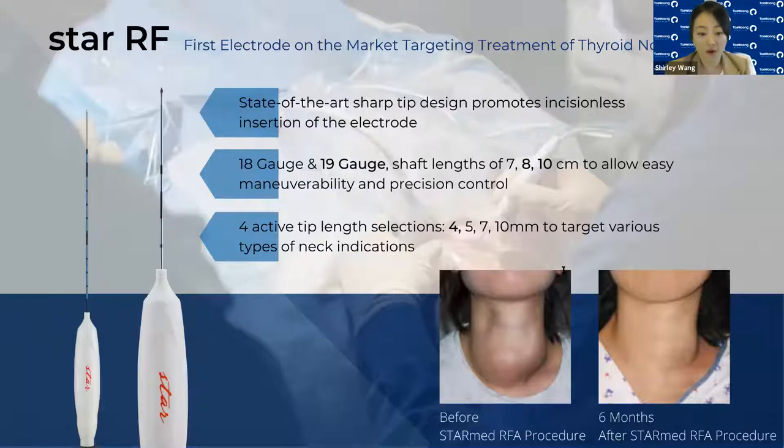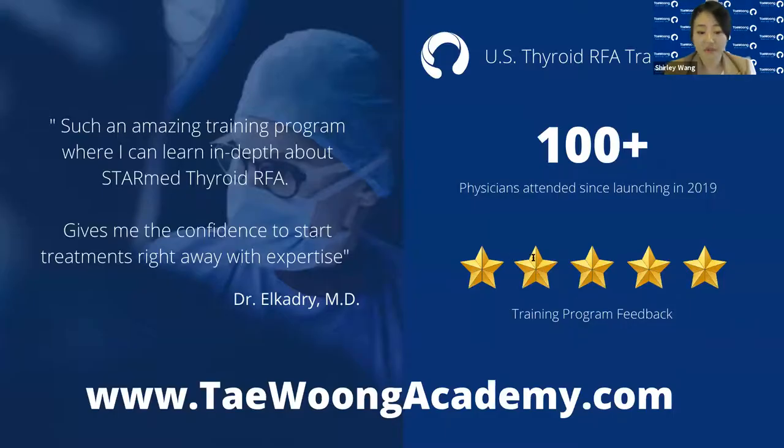We also offer four active tip length selections: 4, 5, 7, and 10 millimeters, to target a range of neck indications from small structures like lymph nodes and parathyroid to large thyroid nodules. Currently, the 4 millimeter active tip size is the smallest tip offered on the market. To facilitate our physicians, we launched a comprehensive thyroid RFA training program in 2019, and since then we have trained over 100 physicians. For more details, you can visit taewoongacademy.com.